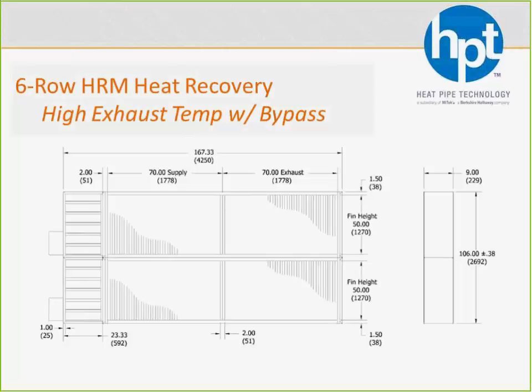Bypass dampers, you can actually select them in our Select Plus software. We will provide them here. We don't have to if it's going in an air handler and the air handler manufacturer wants to provide their own dampers. That's certainly fine with us. We don't make dampers, so it doesn't hurt our feelings, but we do give you that option.